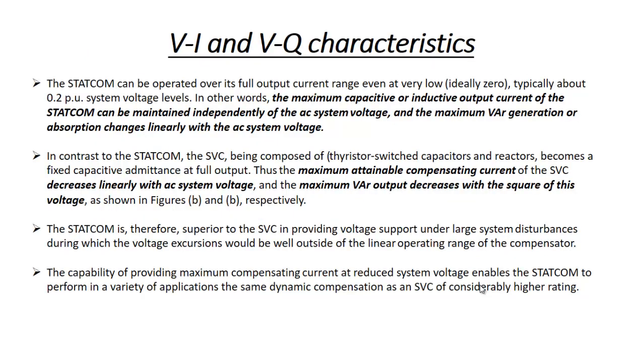The first characteristic is the VI and VQ characteristics. The STATCOM can operate over its full output current range at very low voltage — ideally at zero voltage it can still draw its maximum current, though typically the minimum system voltage level is around 0.15 to 0.12 per unit. The maximum capacitive or inductive output current of the STATCOM can be maintained independent of the system voltage. Maximum VAR generation changes linearly with AC system voltage since reactive power equals current multiplied by voltage and current is constant.